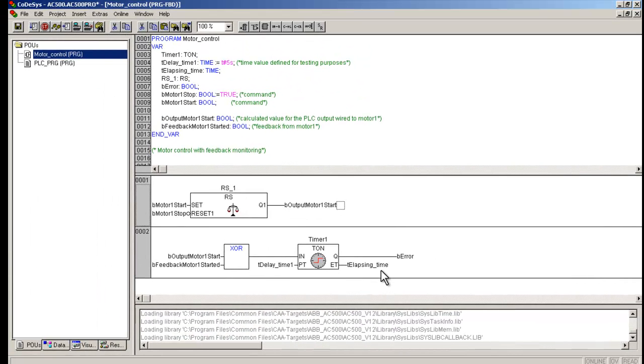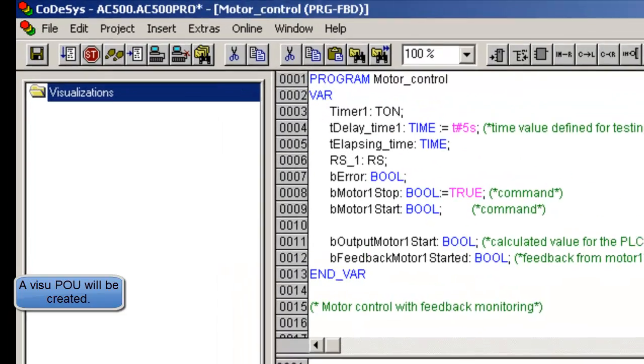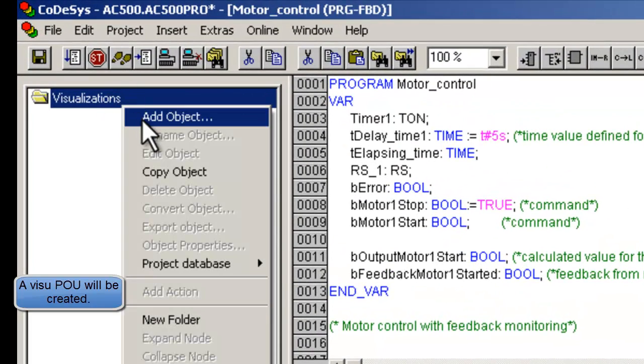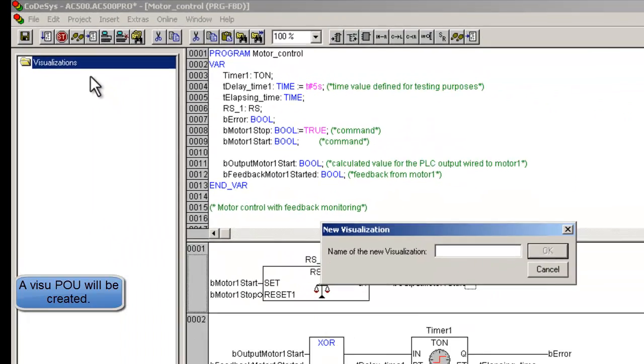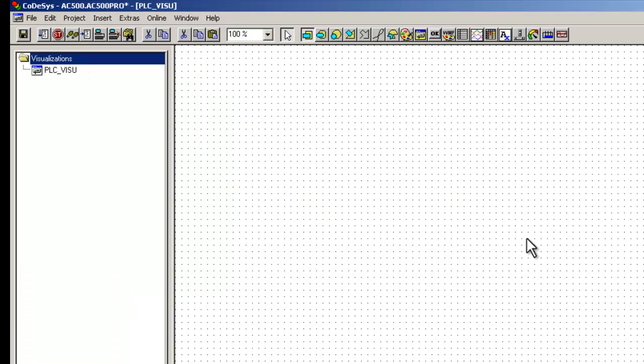In order to create visualization screens, one needs to click on the visualization tab in the CodeSys editor. We create a visualization POU using the add object function. One POU will have only one screen, and we could create as many POUs as needed. The start picture POU must have the name plc_visu, and additional pictures or pages could be linked to this main screen for better navigation.